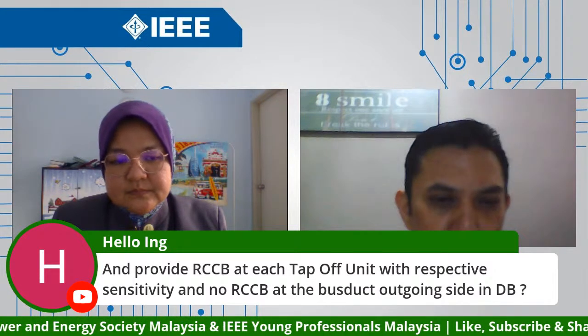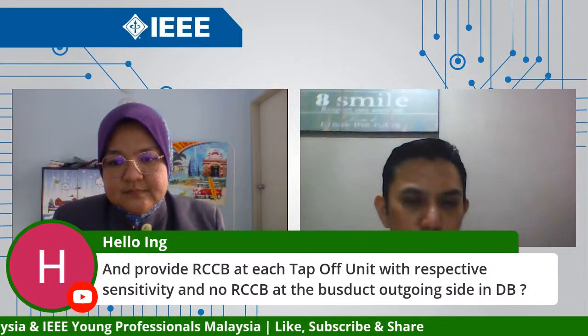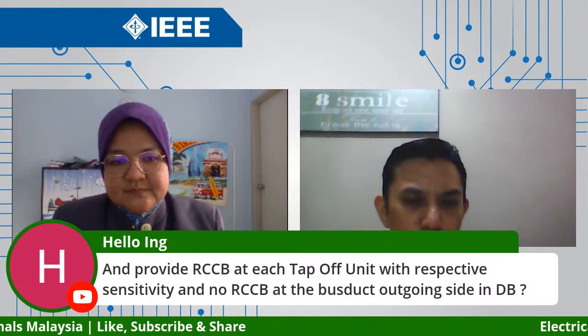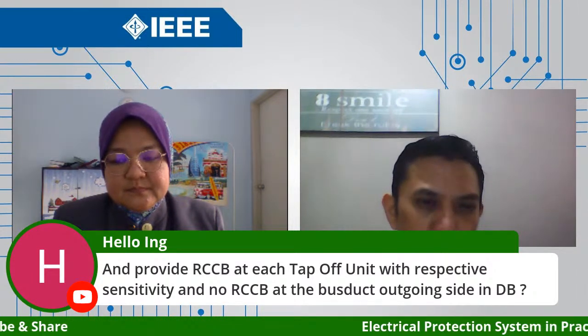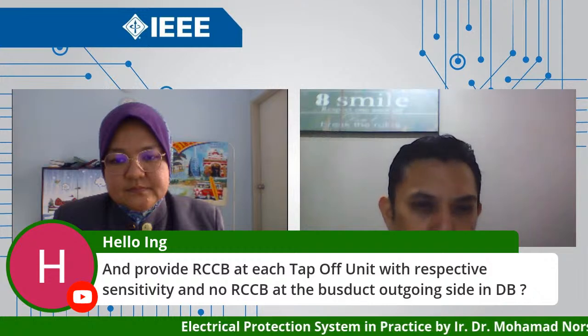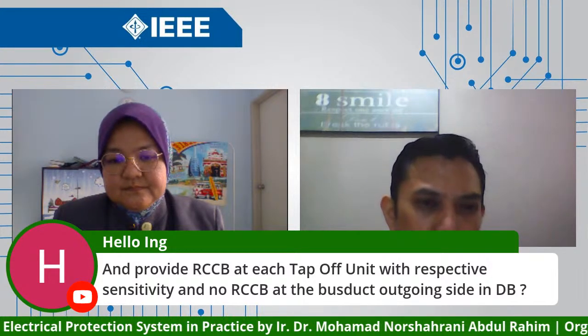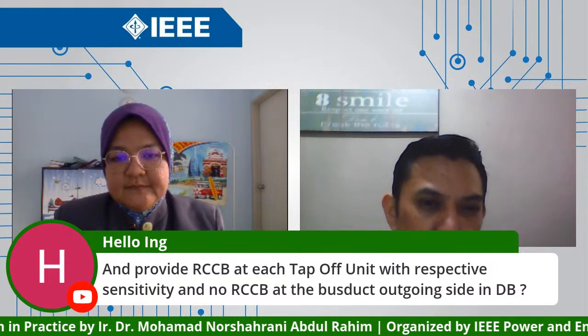Oh, okay. I think if you are referring to the incoming protection and outgoing protection, in the case of a tap-off unit, incoming is sufficient. We don't have to double the protection, incoming and outgoing. Incoming on one side is sufficient. Normally RCCB we install at the final circuit in the DB. So at the tap-off unit, or subboard, we should install ELR, for you to have a good discrimination. Having no discrimination between RCCB and CB is not very good practice.